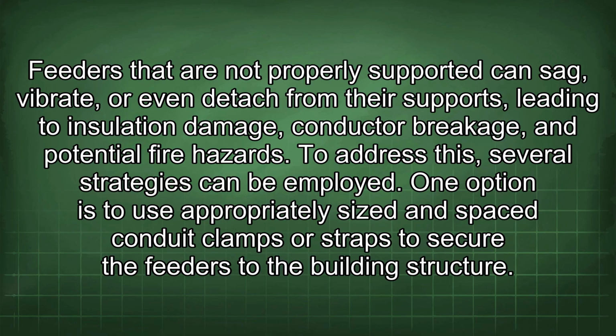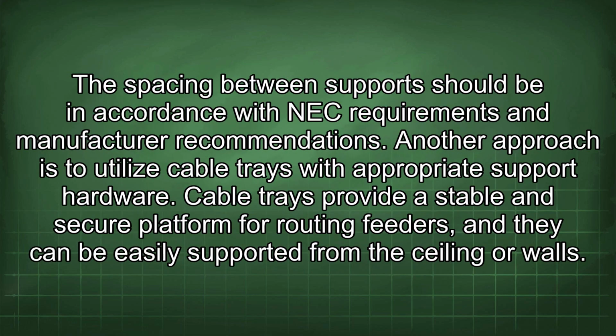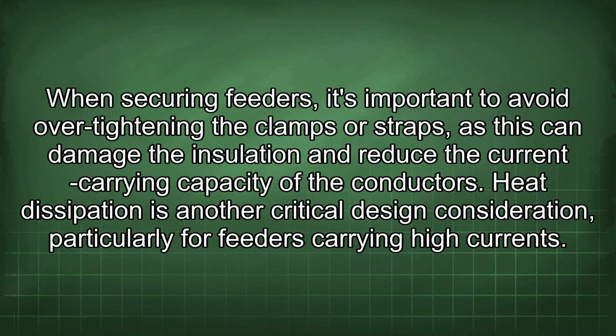To address this, several strategies can be employed. One option is to use appropriately sized and spaced conduit clamps or straps to secure the feeders to the building structure. The spacing between supports should be in accordance with NEC requirements and manufacturer recommendations. Another approach is to utilize cable trays with appropriate support hardware. Cable trays provide a stable and secure platform for routing feeders, and they can be easily supported from the ceiling or walls. When securing feeders, it's important to avoid over-tightening the clamps or straps, as this can damage the insulation and reduce the current carrying capacity of the conductors.